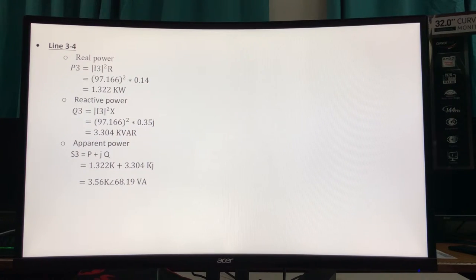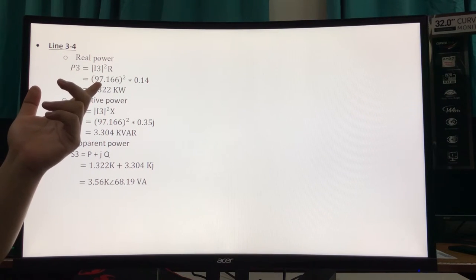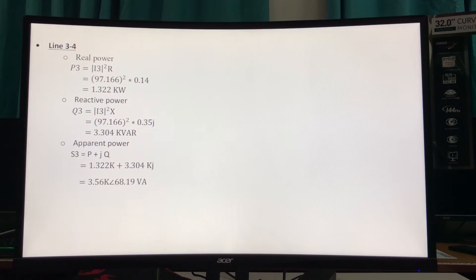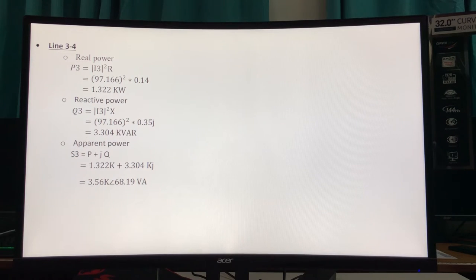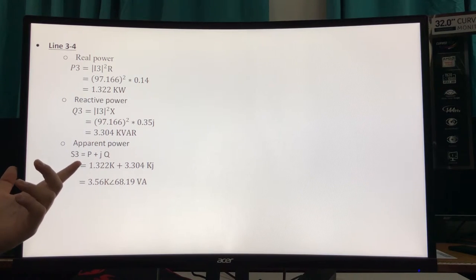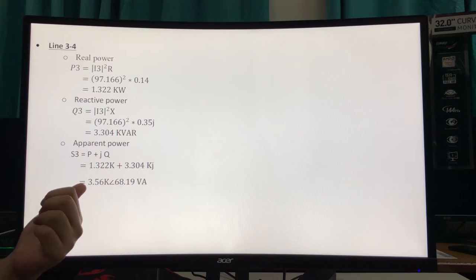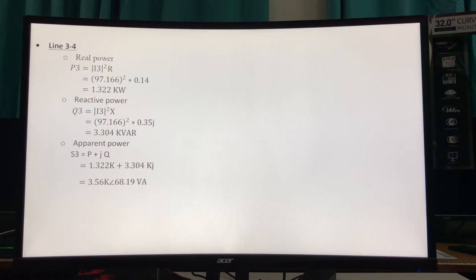Okay, for line 3-4, the real power is I3 modulus squared R. So we use 97.166 squared times 0.14, giving 1.322 kilowatt. Next, reactive power, I3 modulus squared X, equal to 97.166 squared times 0.35J, giving 3.304 kilovar. So the apparent power is P plus JQ, which is 1.322 kilo plus 3.304 kiloJ, and we convert to polar form, giving 3.56 kilo angle 68.19.